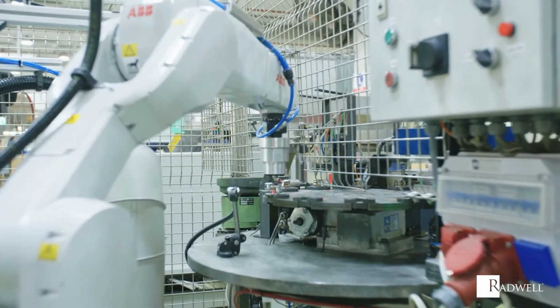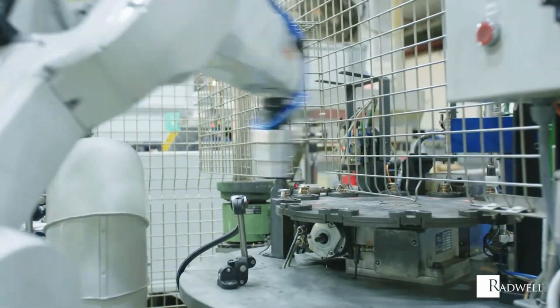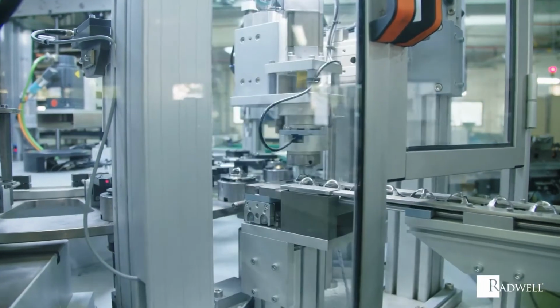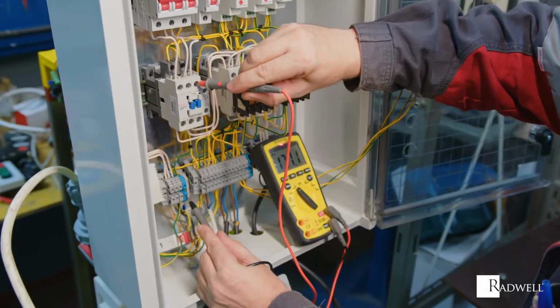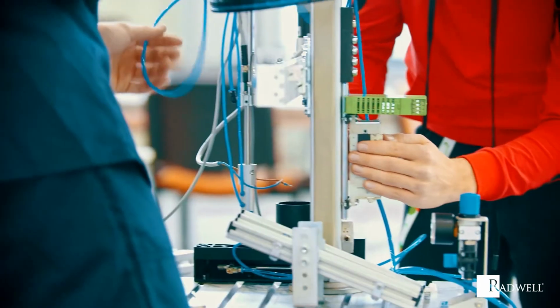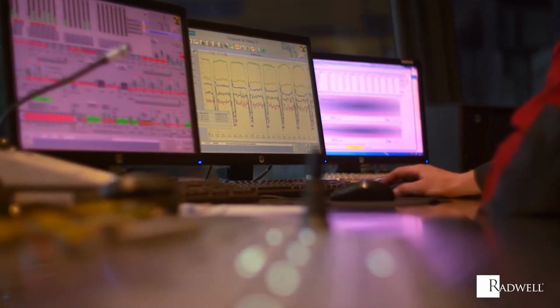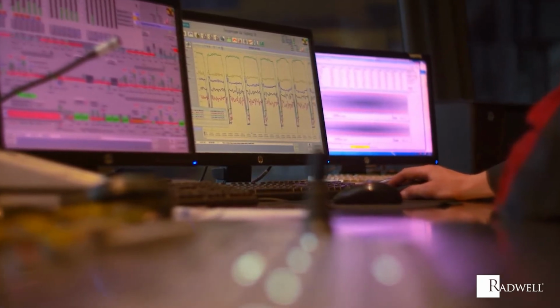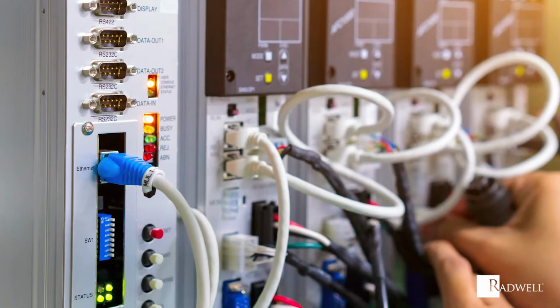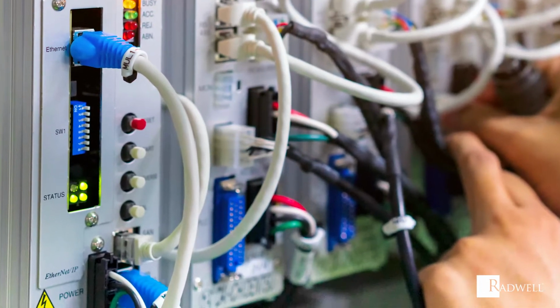There are several advantages to using PACs. They operate using a single platform in multiple domains, such as logic, motion, drives, and process control. Complex and changing requirements can be met with little additional cost. Modular designs make expansion easier. Networking and communication capabilities can link disparate systems and provide more accurate and timely data.